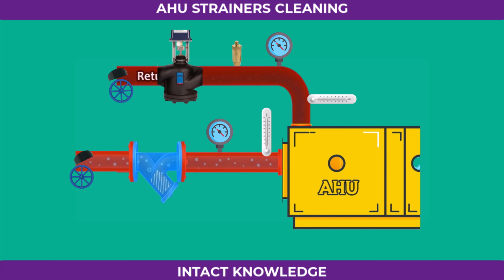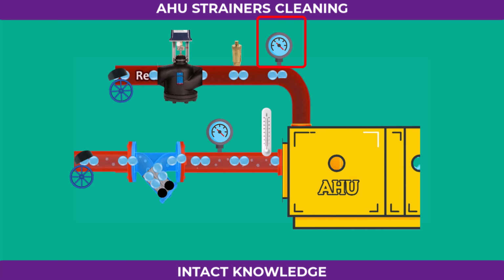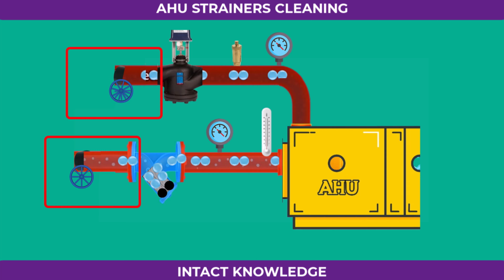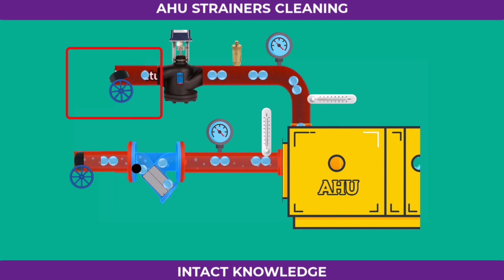If your line doesn't have an air vent, you can remove the pressure gauge temporarily and release air through that point. After ensuring all the air has escaped, fully open the supply valve, then open the return valve completely. Now, water will circulate smoothly through the entire system. And that's the correct method for cleaning the strainer in an AHU pipeline.